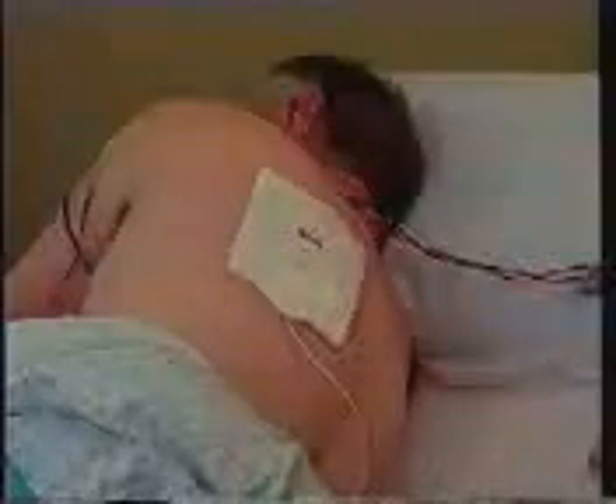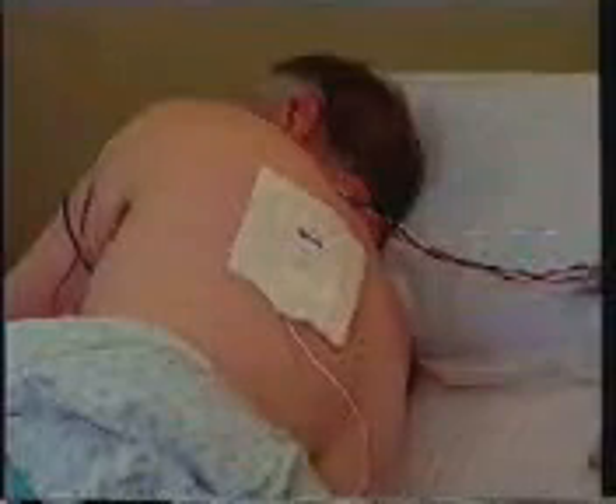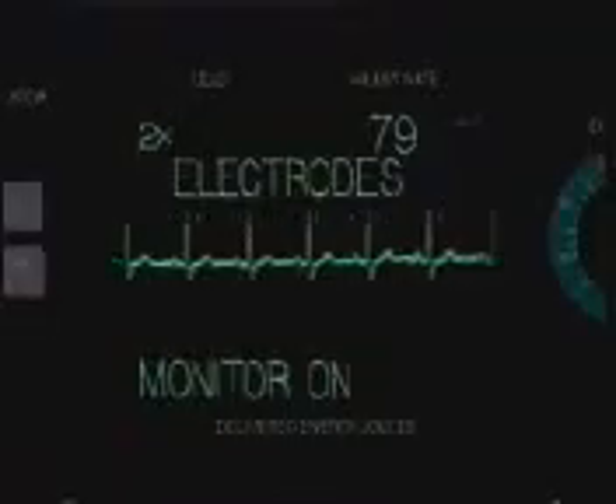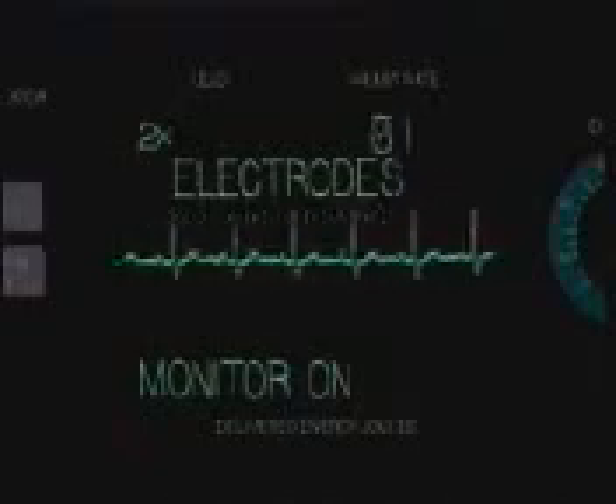The monitor, defibrillator, or the pacer are immediately available and may be changed at any time to properly treat the patient's rhythms. The initial lead source is through the multifunction electrodes in the monitor or defibrillation mode. You will visualize a modified lead 2 tracing.